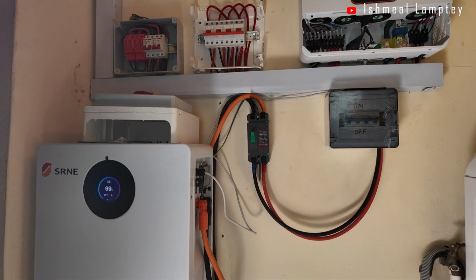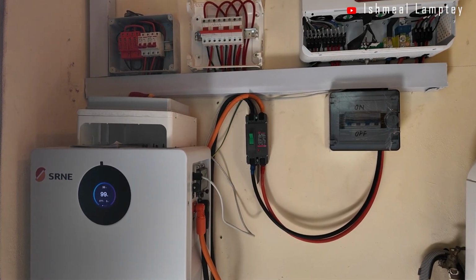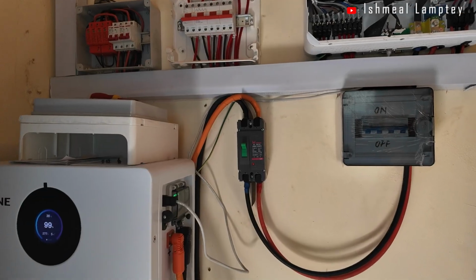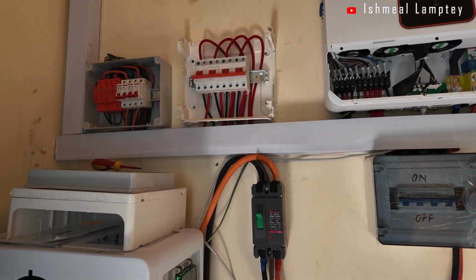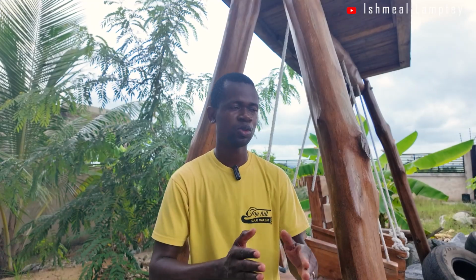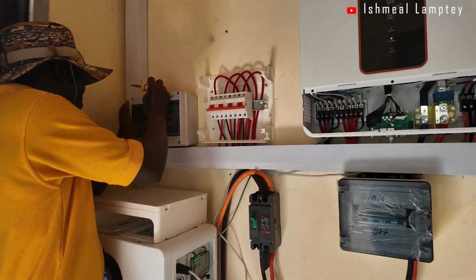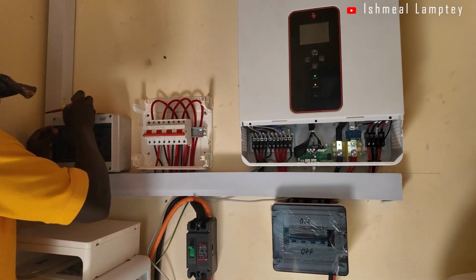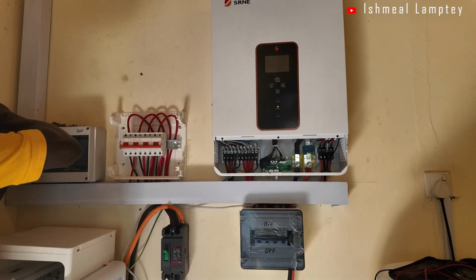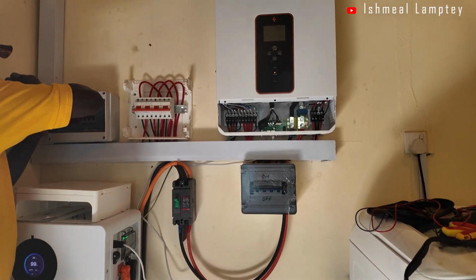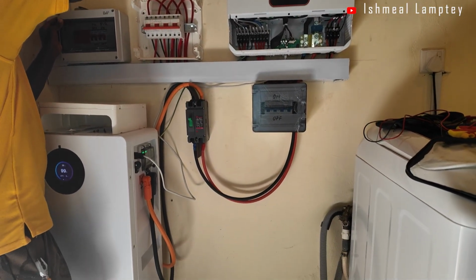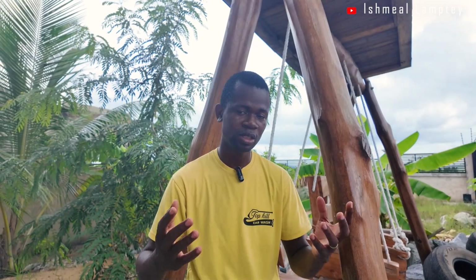After doing that, we went ahead to mount the inverter on the wall. After mounting the inverter, we had different breakers doing different things, which I'll explain, also mounted on the wall. So we had the breaker boxes mounted on the wall: a breaker box for the panels, a breaker box for the changeover, and a breaker box for the AC input. Now, this inverter already has a breaker for the AC input, but it's always best to have an additional line of protection for such systems.